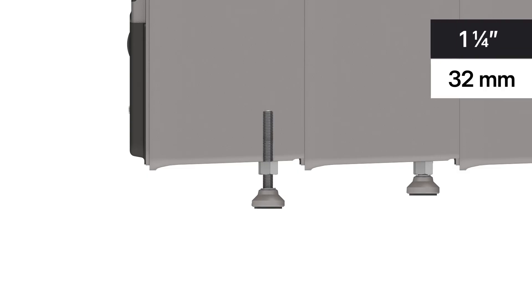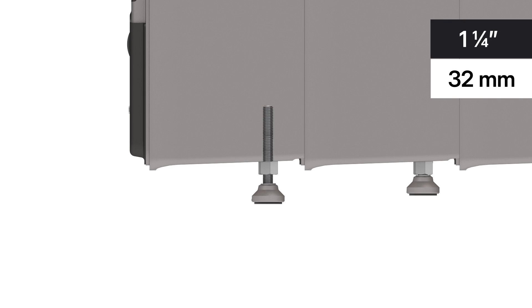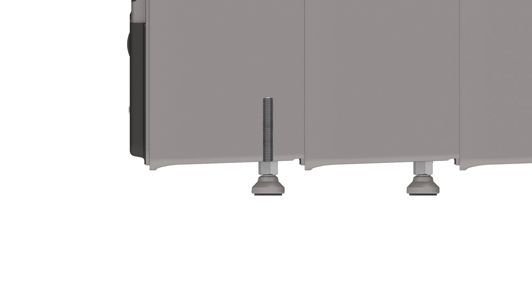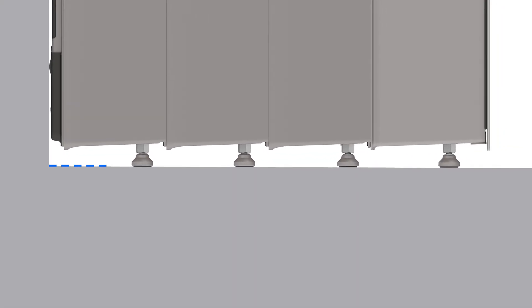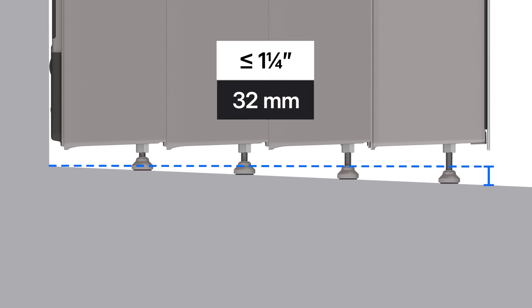The feet on Powerwall can be adjusted up and down by the maximum amount shown here. Keeping that in mind, the slope of the floor will need to be assessed to ensure that the lowest point of the stack will be within this range.